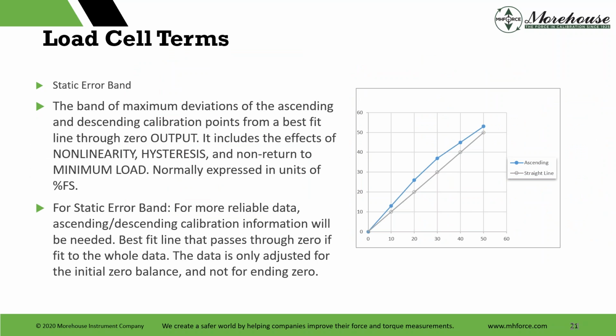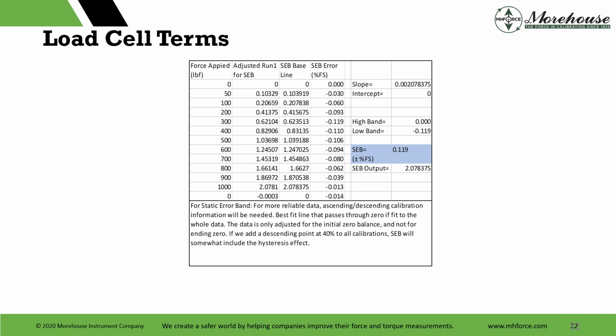That's all it is. And then we're talking about static error band. This is the band of maximum deviations of the ascending and descending calibration points from a best fit line through zero output. It includes the effects of nonlinearity, hysteresis, and non-return to minimum load, normally expressed in units of full scale. And for more reliable data, ascending and descending calibration information will be needed. Best fit line that passes through zero. If fit to the whole data, the data is only adjusted for the initial zero balance and not for the ending zero. So when we do this in the data here, slope, intercept, we're using something similar, an Excel function called LINEST to do this.